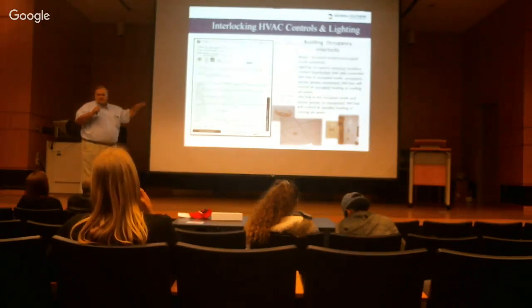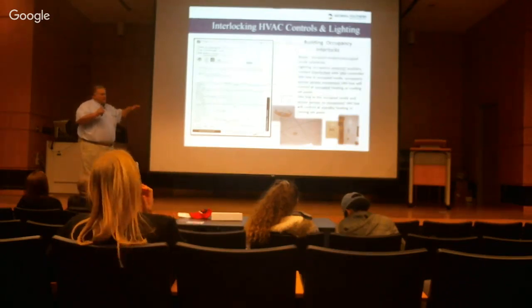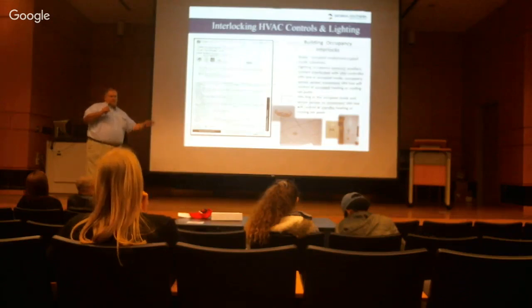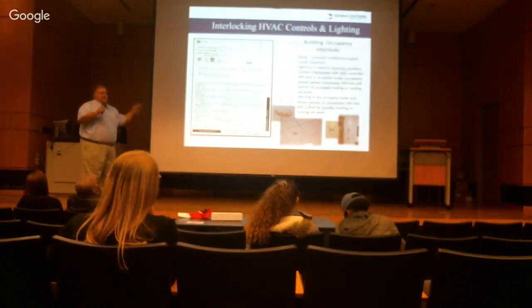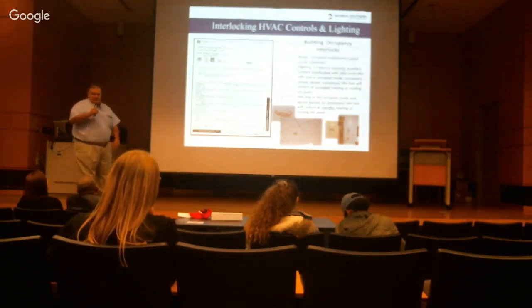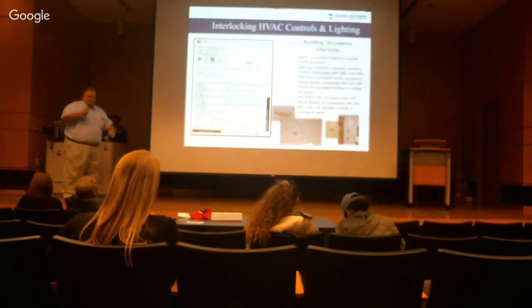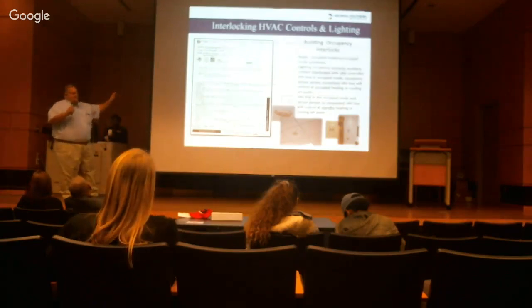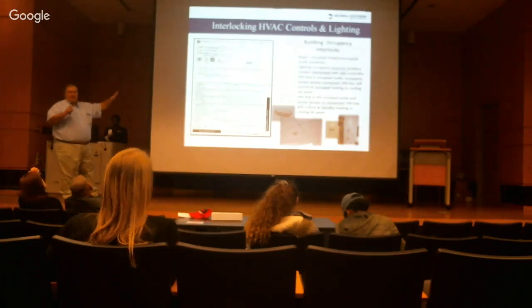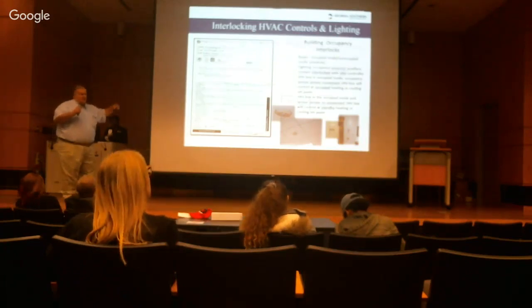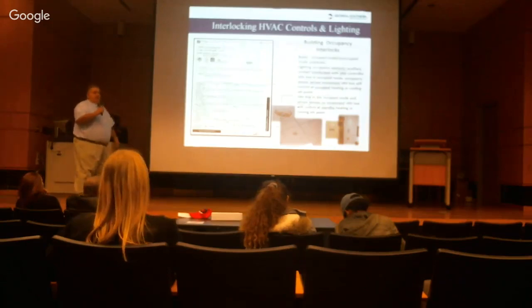Most people don't know that — they don't even sense it happening. It throttles all the way back through the system, through the air handler, slows the motor down, trims the chill water valve, and trims the chiller down so it doesn't run hard. It's a huge energy savings, and it runs all the time without people noticing. It doesn't really impact them much. We also use it in our load shedding scheme.